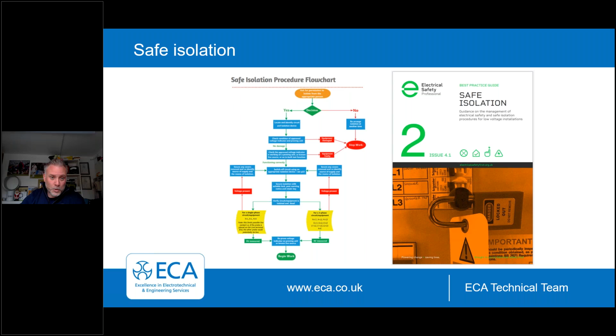So looking at this in more detail, yes, we're going to ask for permission from the appropriate person or persons to turn off, to isolate those circuits. And if you don't have permission, then you're not going to do the works. But providing you've got permission, then you're going to locate and identify the circuit and use an isolation device. You're going to prove your tester works via a proving unit. So test your equipment, make sure it's all good. Okay. You're going to switch off the device and you're going to put an approved lock-off kit on.